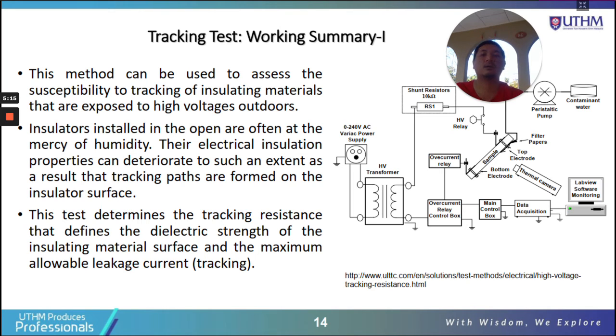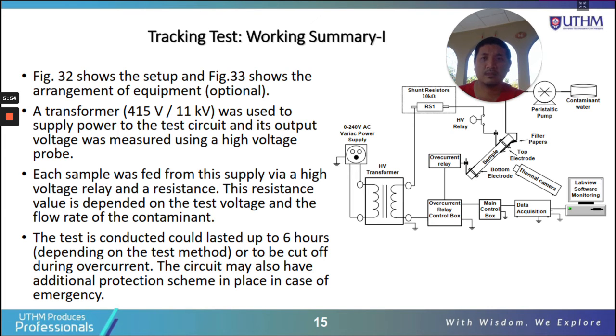So basically, because of the humidity, because of the rain, over time there is tracking on the surface of the insulation material. That can result in flashover or full breakdown of the material. So the test determines the tracking resistance that defines the dielectric strength of the insulating material surface and the maximum allowable leakage current. So this is the setup.